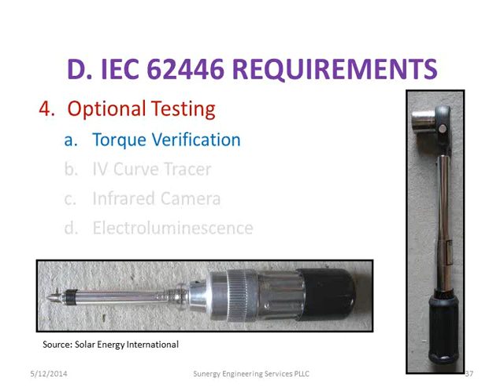But what's happening nowadays, a lot of people are using infrared cameras after that initial test to go back for their annuals, because they can take an infrared picture and they can see if there's a loose connection because the wires are going to be running a lot hotter. And that way they don't have to retorque them every time. And a lot of times maintenance plans will actually be based on what the temperature difference is. A certain temperature means, okay, whenever the maintenance guy gets there, have them check this one. Or if it's a higher temperature, they go, oh, this is really hot. We need to shut this down. We need to get somebody here to fix this right now because this is way too hot.